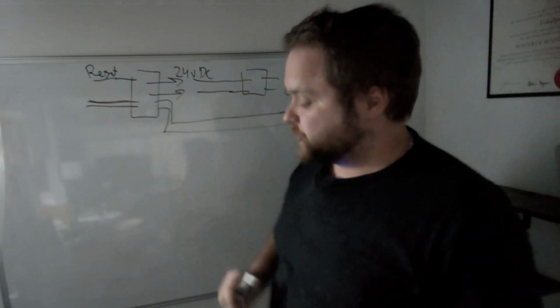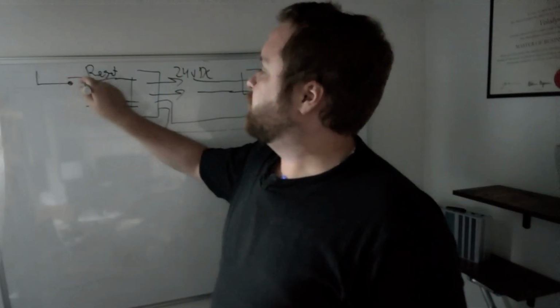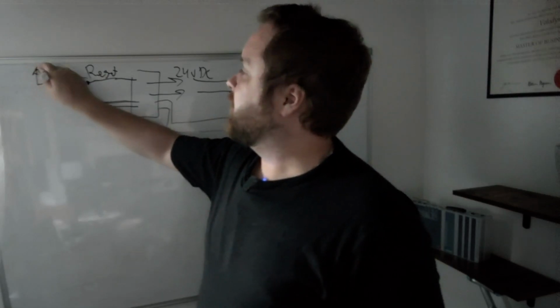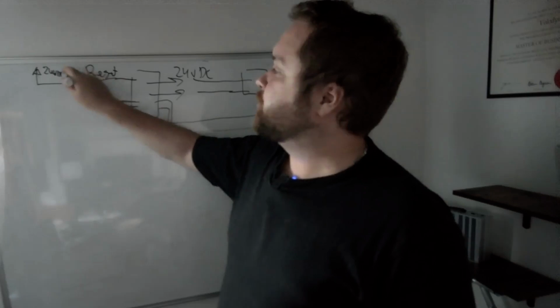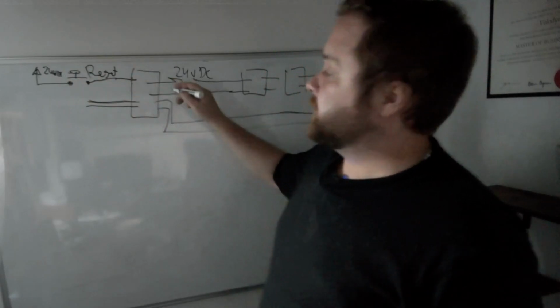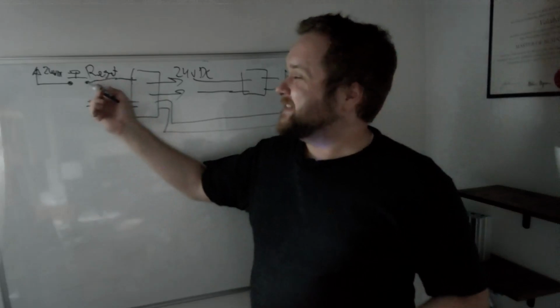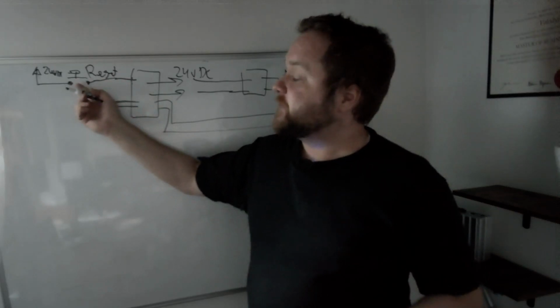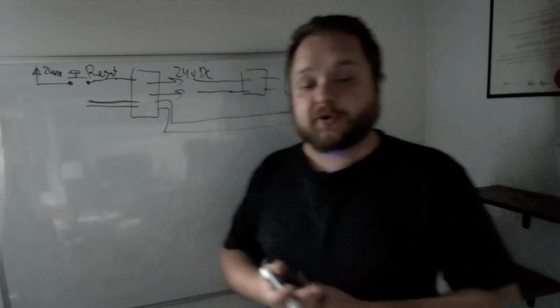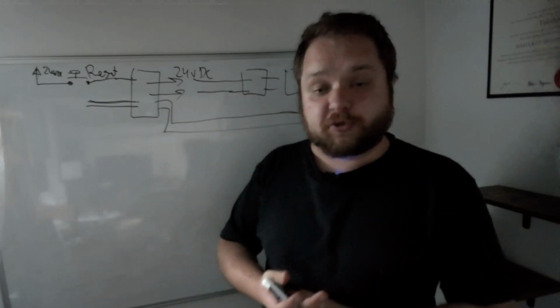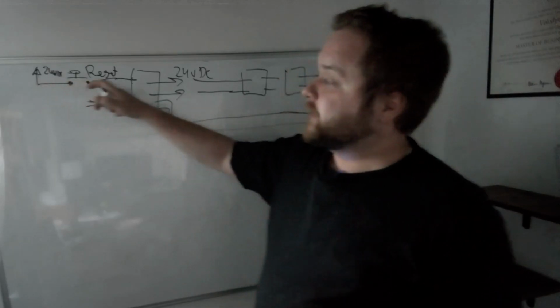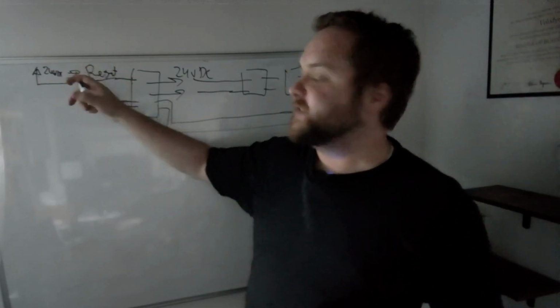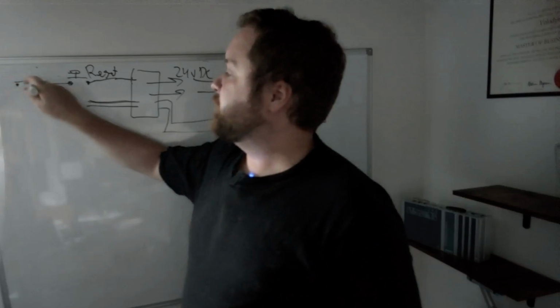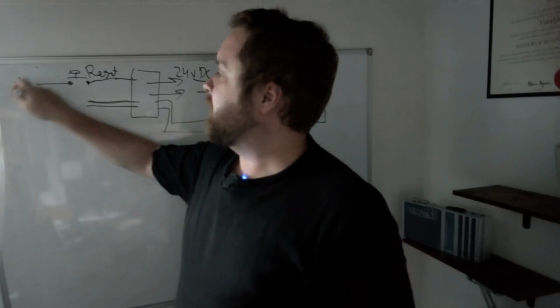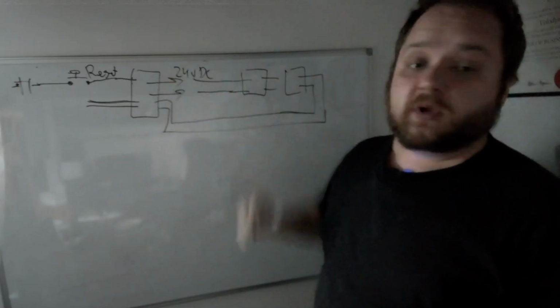So I want to revisit this reset function just a little bit. This can be a push button, and a lot of times you will see this in automation. If somebody pushes this push button, it's going to close the circuit, and if everything is good, allow it to reset. Of course, you can put different things in series with this specific reset. So you can add checks, for example, on your PowerFlex drives. You can add other checks in your software. So understand that this circuit is not necessarily safety rated. So your reset can be based on a variety of signals, and you can add different things as part of the circuit. Again, this could be switches, this could be contacts, right? So I'm going to just add a contact here that needs to be made in order to allow the reset.